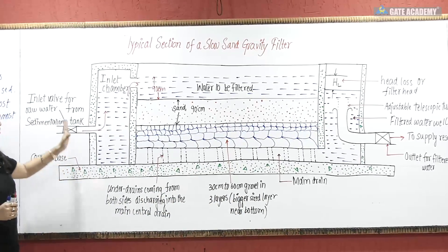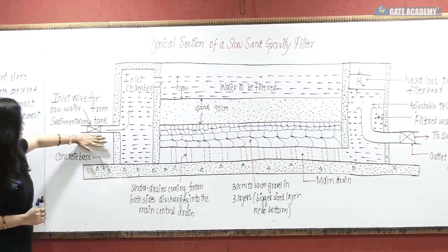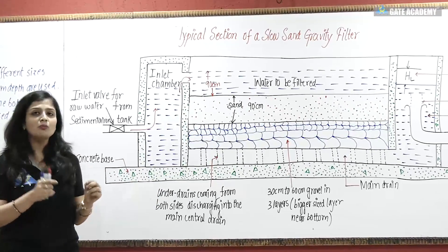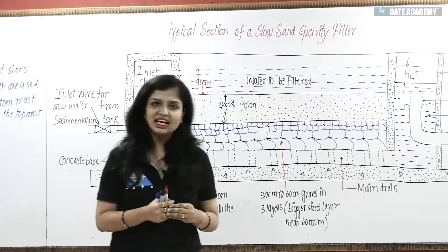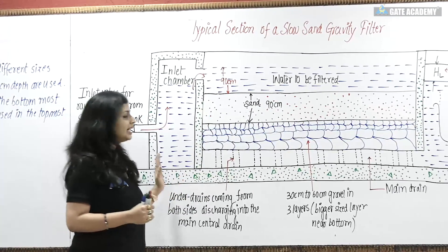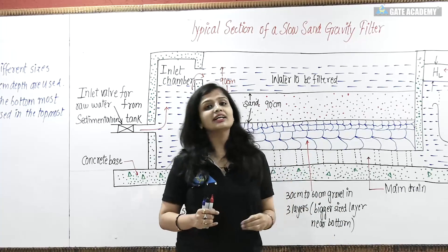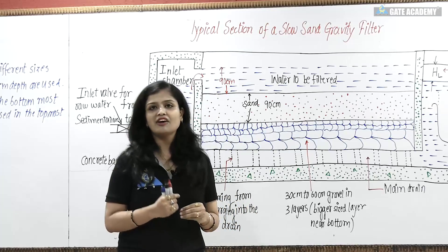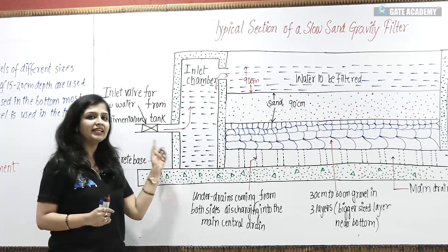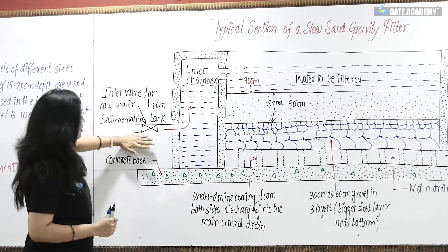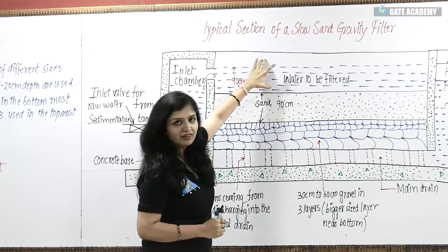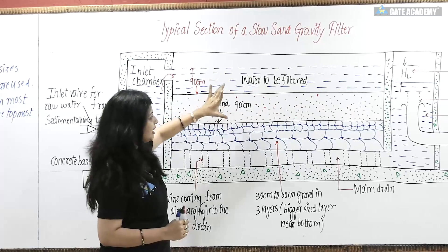Now I will label all the components of the diagram. First, this is inlet water, which comes from the sedimentation tank. For the slow sand gravity filter, we use water from plain sedimentation only — we do not use water treated by sedimentation with coagulation, because sedimentation with coagulation leads to clogging of the filter beds. This is the inlet valve, below our concrete base. This is the inlet chamber. This is the sand layer and this is the gravel layer.